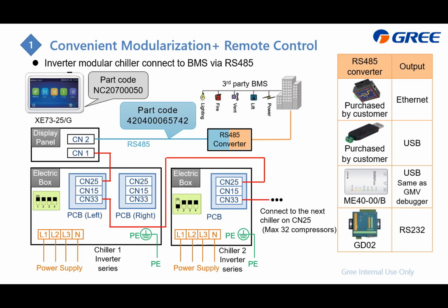On this slide, you'll find that here is chiller number 1, and this is chiller number 2. This is our latest chiller, which has 2 compressors and 2 PCBs, and the left side is the master. For the modularized connection, you need to connect from chiller number 2, the CN25 here, to the first CN33. If there are 2 PCBs, select the left side. On the other hand, don't forget to change the dip switch.